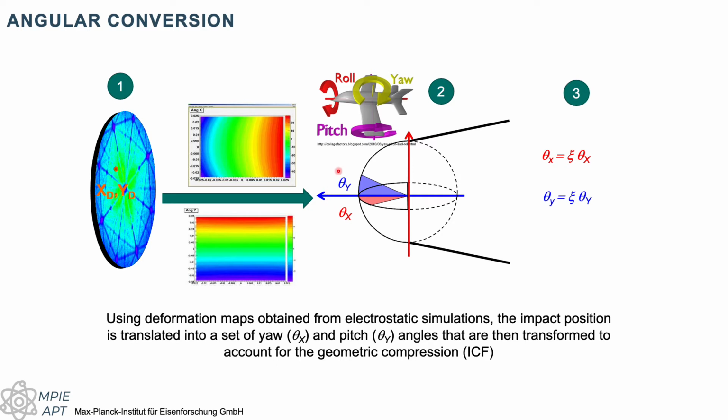Here, the correction in the y-axis or the x-axis will not be the same, because the ions in one direction will be returned and in the other one it's just not as vastly affected. So we typically need to assume these differences in the compression of the trajectories and in the times of flight, which need to be corrected slightly differently.